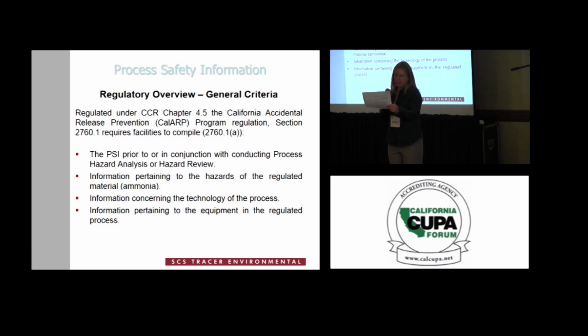Has the employer documented that the equipment complies with recognized, generally accepted good engineering practices? This is one that has the letter. Yeah, the contractor provided all those nice handy-dandy letters. So that makes it really easy. I've seen some facilities hire in an engineer to go through some code compliance or put their PE on it, but I thought the letter was pretty nice and handy to have.